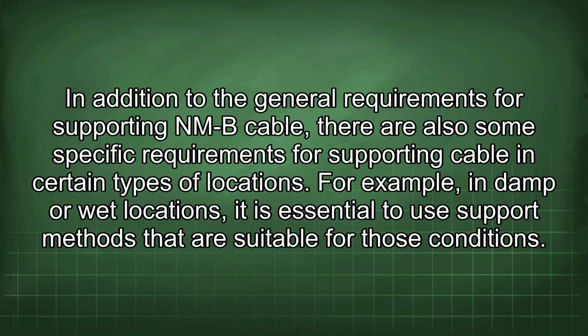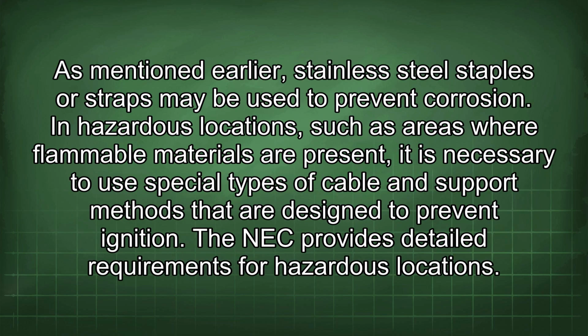In addition to the general requirements for supporting NMB cable, there are also some specific requirements for supporting cable in certain types of locations. For example, in damp or wet locations, it is essential to use support methods that are suitable for those conditions. As mentioned earlier, stainless steel staples or straps may be used to prevent corrosion. In hazardous locations, such as areas where flammable materials are present, it is necessary to use special types of cable and support methods that are designed to prevent ignition. The NEC provides detailed requirements for hazardous locations.